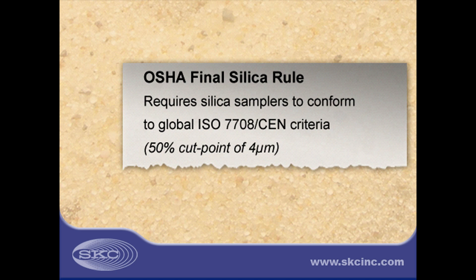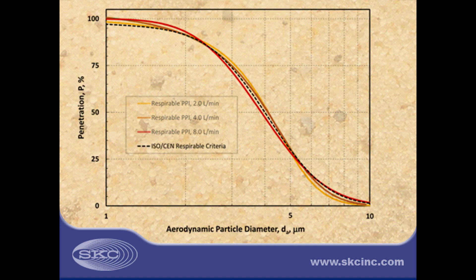Silica samplers must conform to the ISO/CEN criteria with acceptable levels of bias. The new SKC PPI samplers are specifically designed to match the ISO/CEN criteria and are described in the final Silica Rule. OSHA notes that personal impactors are available for use at flow rates from 2 to 8 liters a minute and have been shown to conform closely with the ISO/CEN criteria.